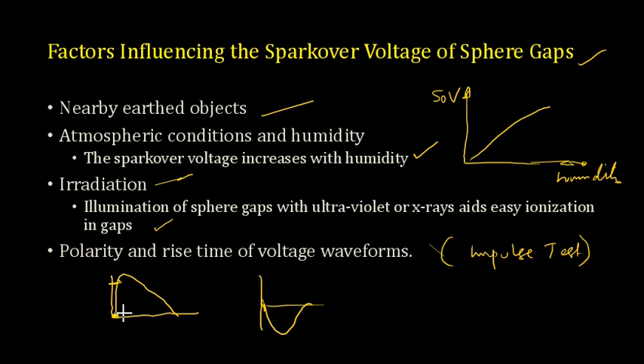So rise time is defined for each waveform, and for impulse also a standard rise time is defined. Rise time is how quickly your voltage is increasing from 0 to maximum value, or 90% of maximum value. So in different ways you are identifying the rise time. Such polarity as well as rise time will be affecting the flashover voltage or spark over voltage of sphere gaps.